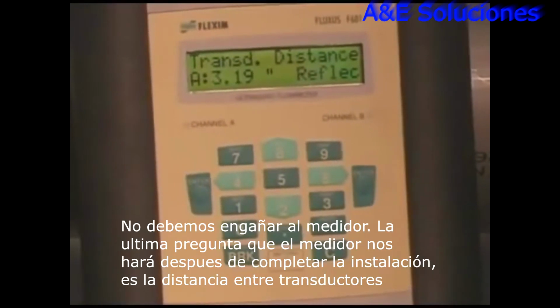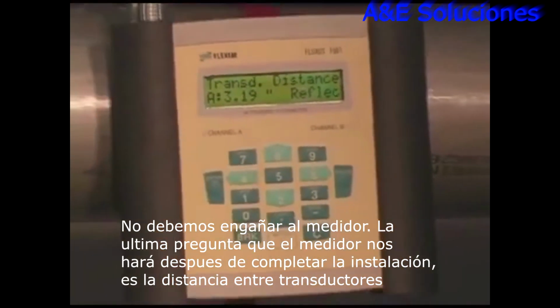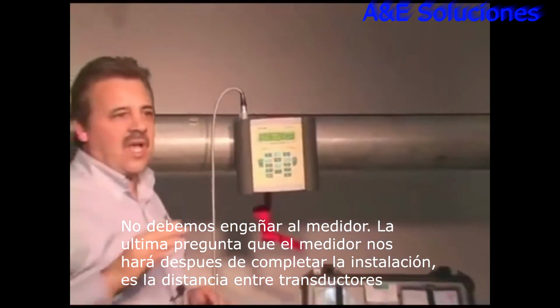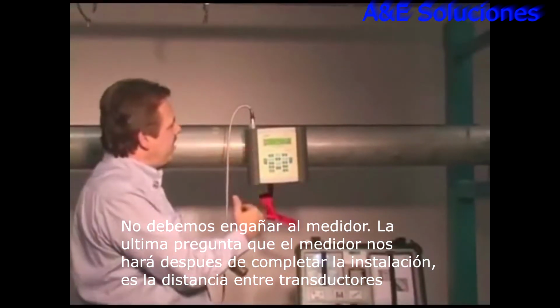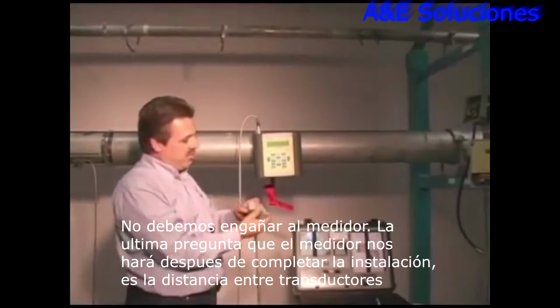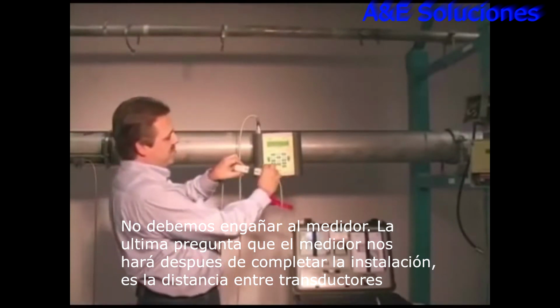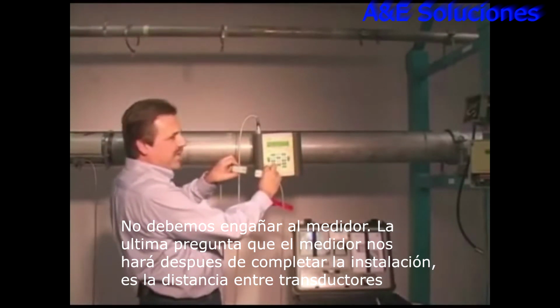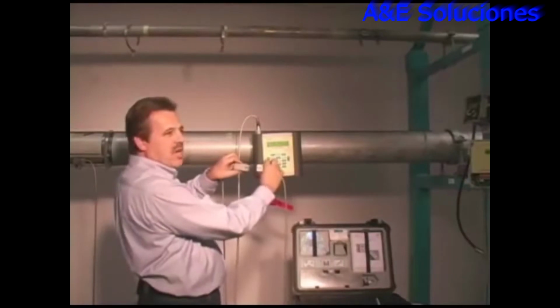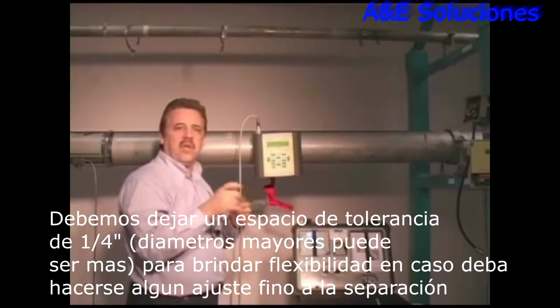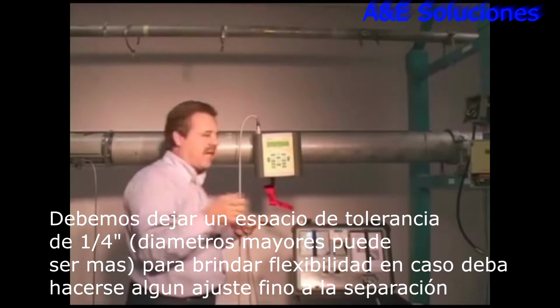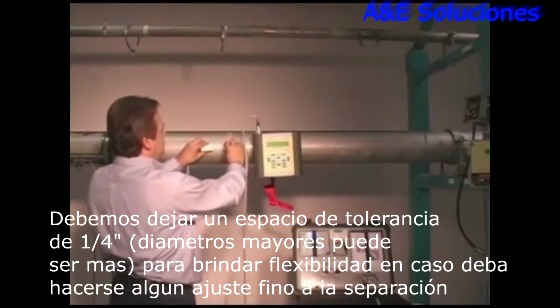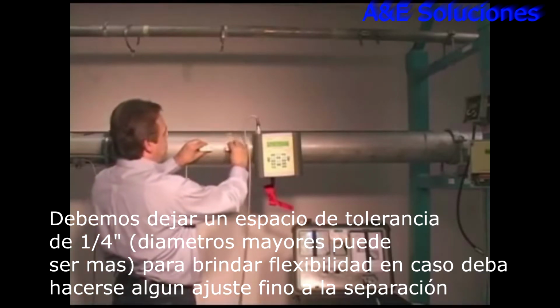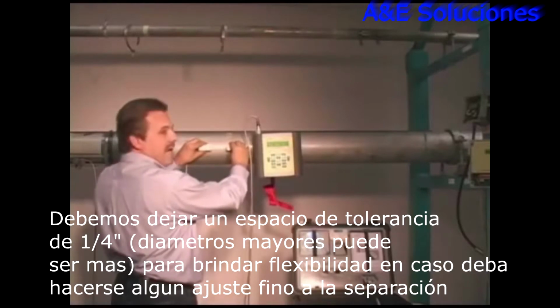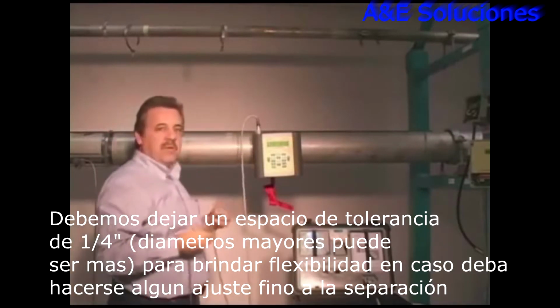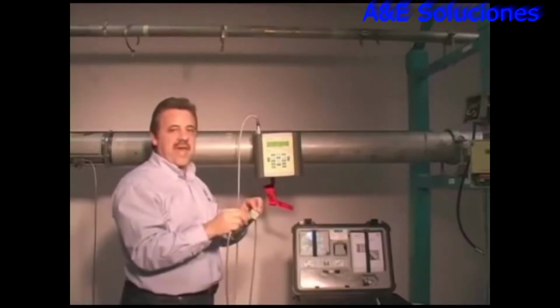Now, we won't cheat the meter. The last question the meter will ask us after we've completed the install is, what did we actually space the transducers at? So we have some flexibility, easily a quarter inch, but on larger diameter pipes we can get a little bit more flexibility on the spacing there. And sometimes we can even use that flexibility to fine-tune the signal to peak it out.